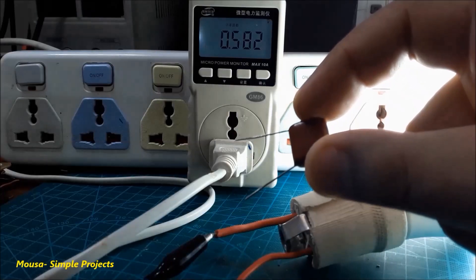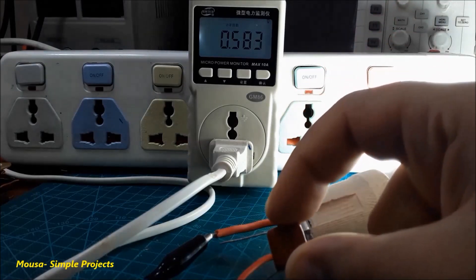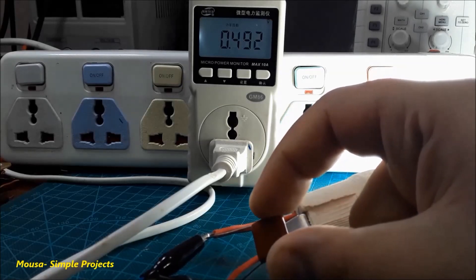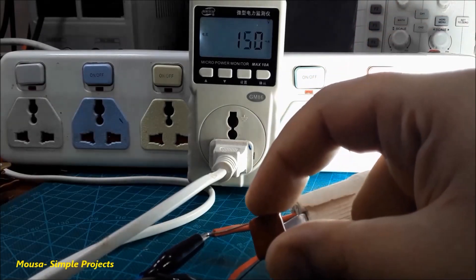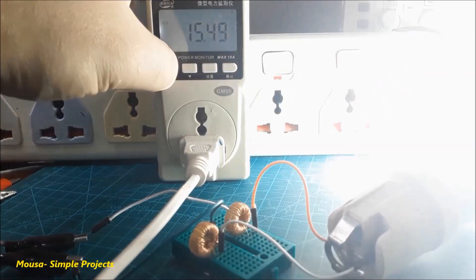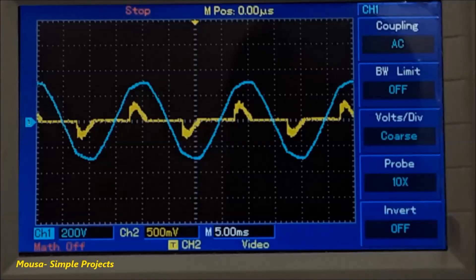You cannot use the same method for improving the power factor of LED lamps. By adding a power factor correction capacitor across the LED lamp, the power factor becomes even less and the drawing current becomes even higher than before. Adding an inductor also cannot be useful because the current phase in LED lamps is not sinusoidal. This kind of electric load is called a non-linear load or harmonic load.